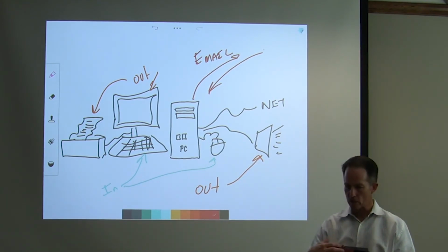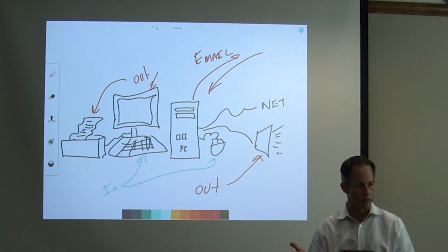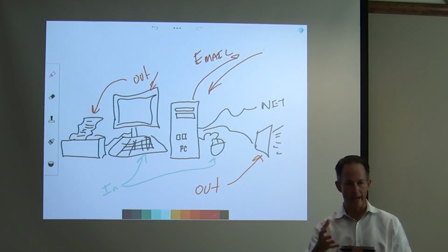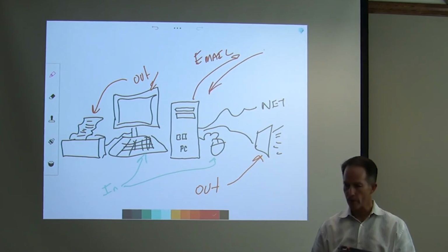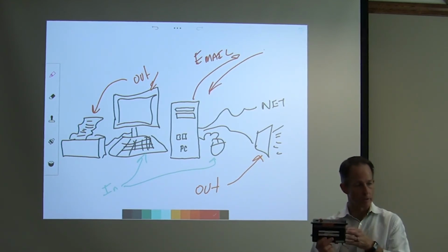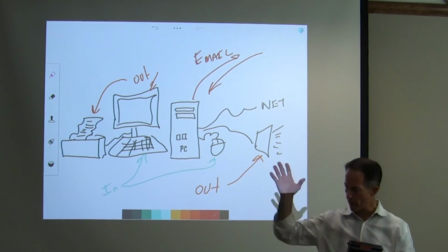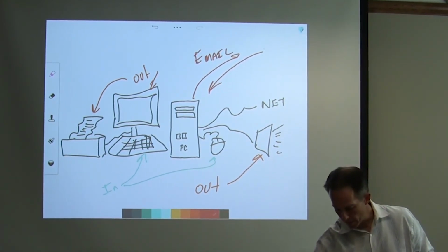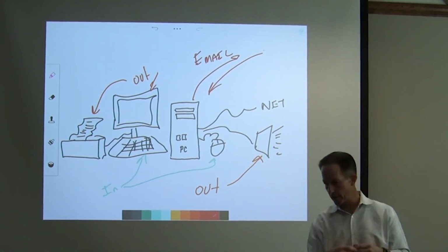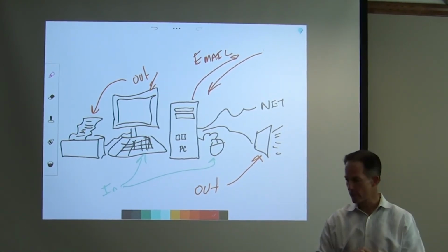The JACE, which is the Java Application Control Engine, and the supervisor, which is, we hear the term N4 for Niagara 4 or AX. AX is the third generation, N4 or Niagara 4 is the fourth generation of software. That's the same thing that runs inside of these JACEs, just we put it on a computer to do our supervisory stuff. And that has the ability to bring it all together and to communicate.